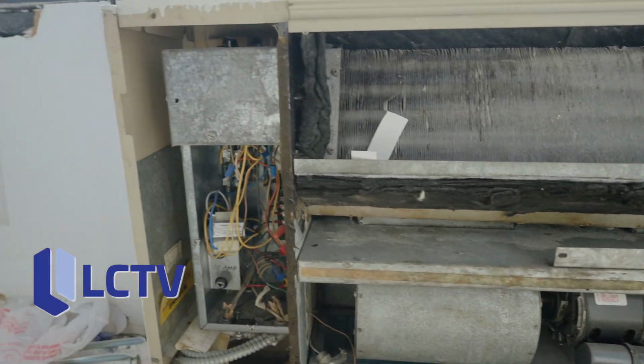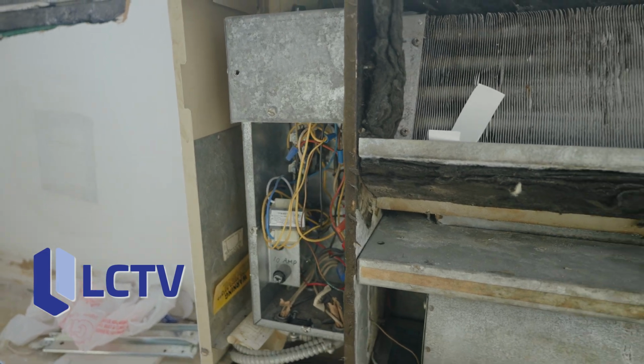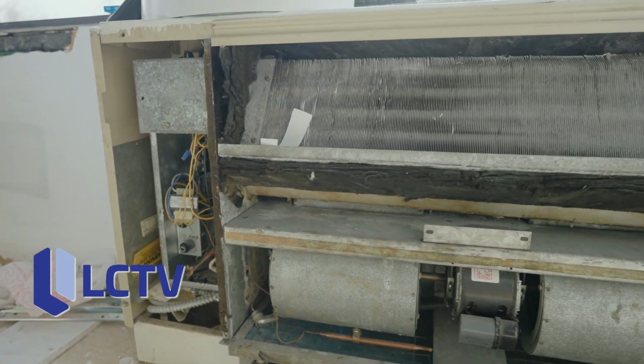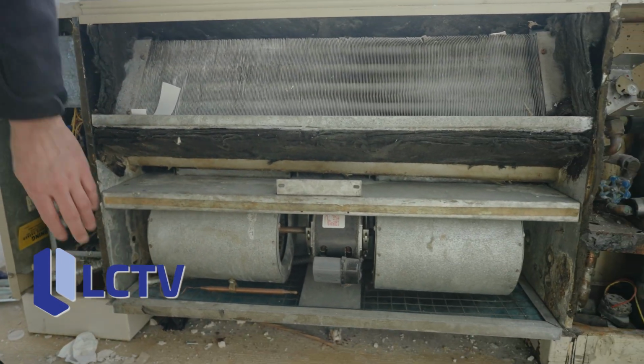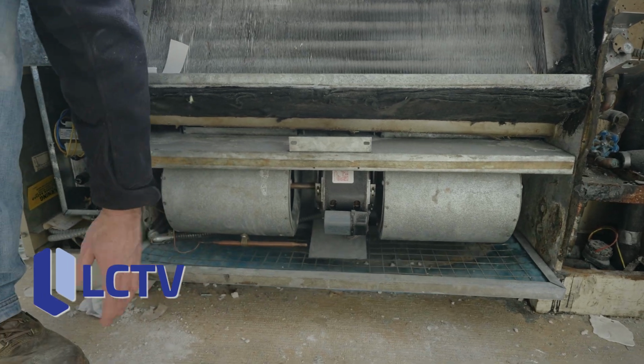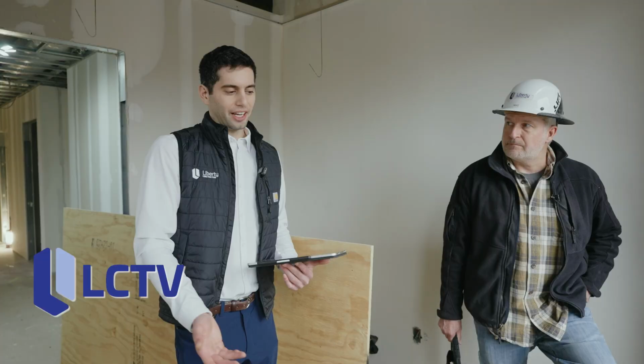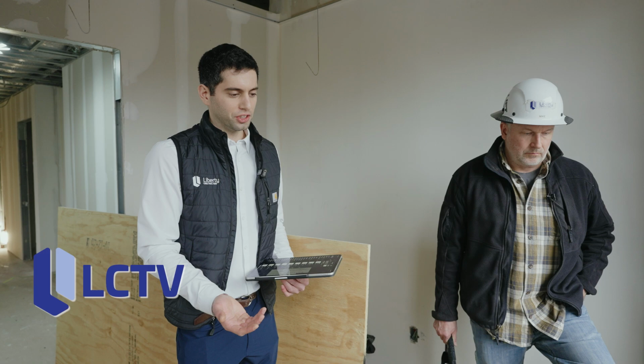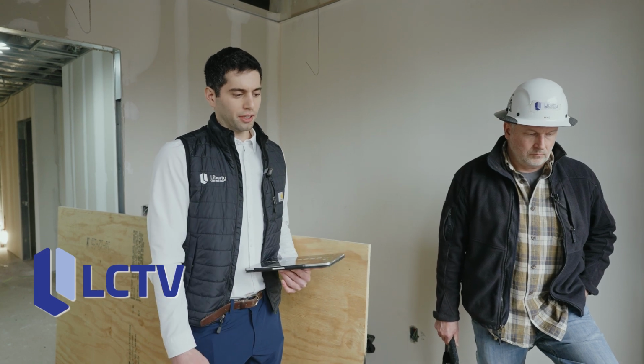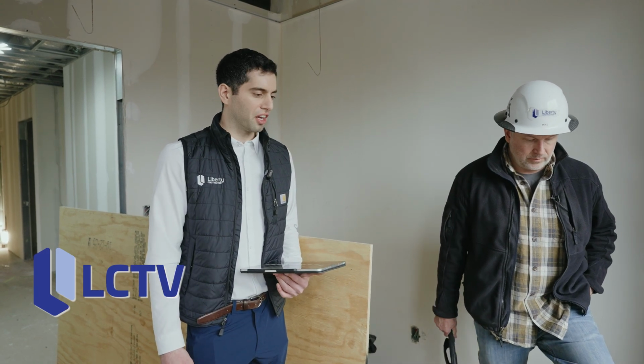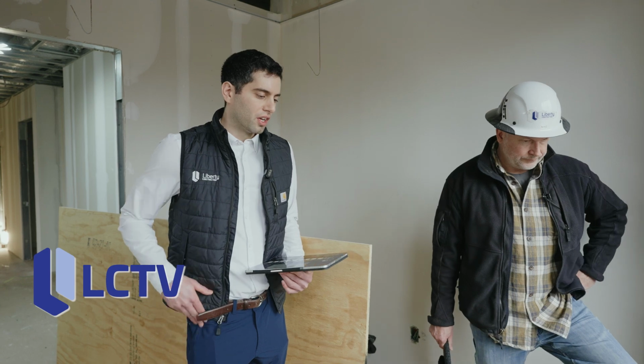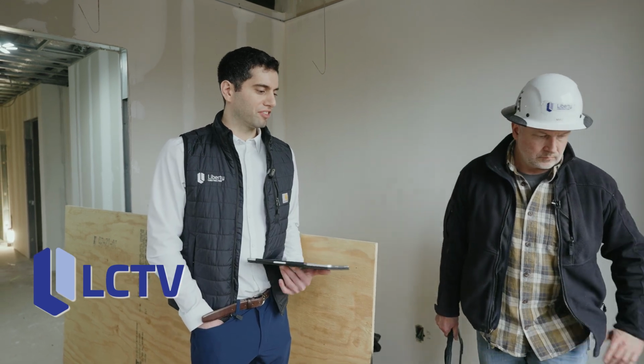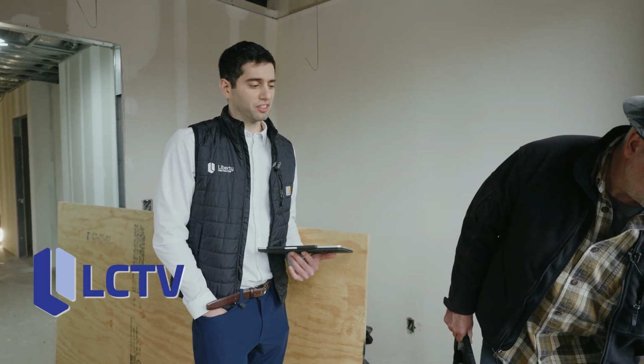At the beginning of each project, if it's a fan coil, we'll do water balancing to make sure the coils are actually supplying the hot and cold water at the temps needed. Otherwise it's just going to be ambient temperature and not do its job. But they're pretty simple - just filters and water loops that need to be tested for temperature. They have a lifespan of 20 years, honestly.